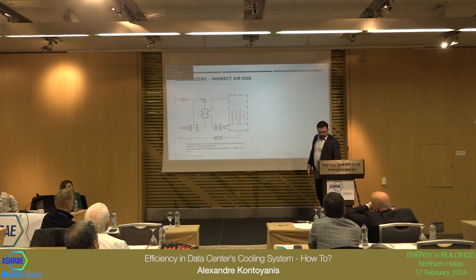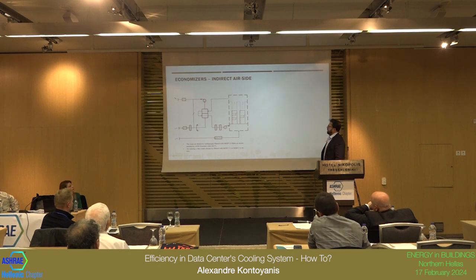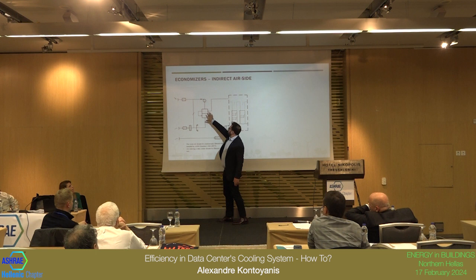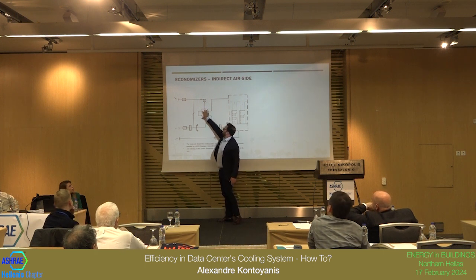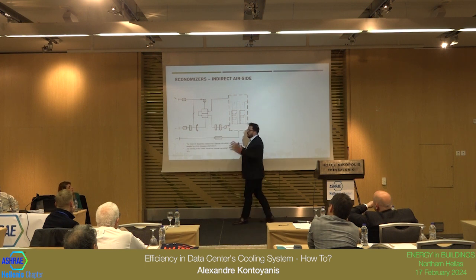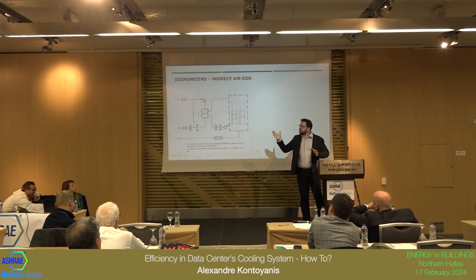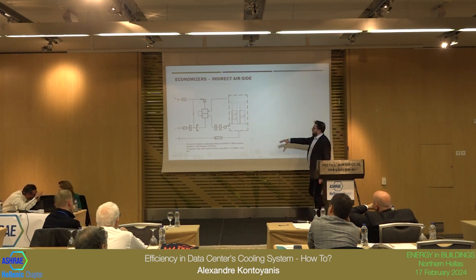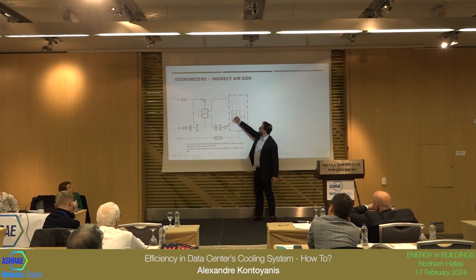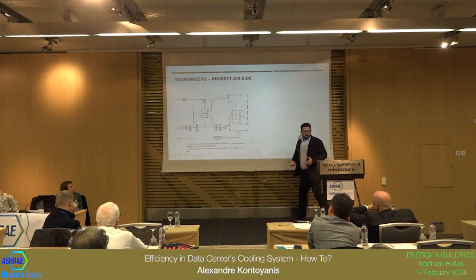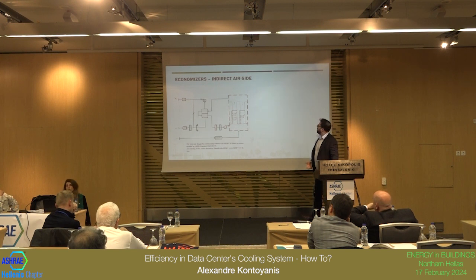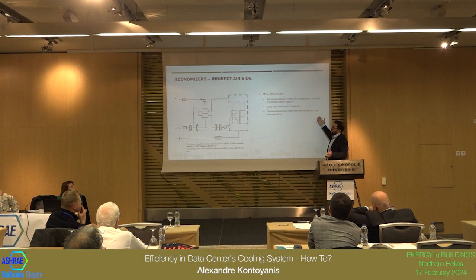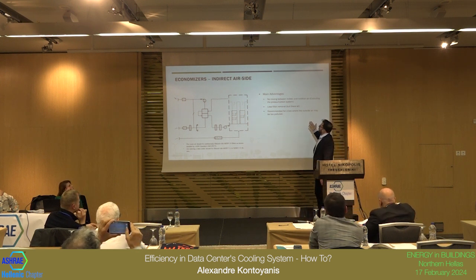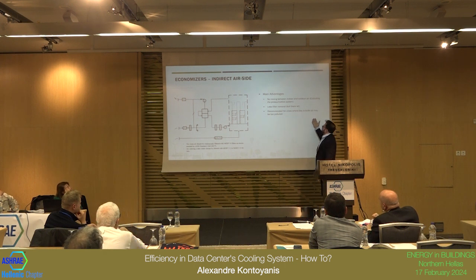Okay. And we have the indirect airside economizer. Can you see the difference here? The difference is we now have a heat exchanger here, an air-to-air heat exchanger. Now we no longer mix the air between the outside air and the inside air. Of course, you have some air coming from outside to pressurize the place, but it's just a little bit. And the main advantage, I think, is that you no longer mix the air streams. You use fewer filters. And it's recommended for cities where the outside air may be too polluted or too humid.